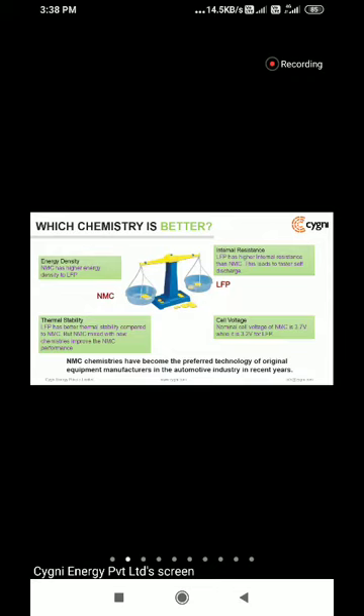Even when we look at the previous slide, the thermal runaway parameter is also not too far apart. LFP has thermal runaway at about 270 degrees centigrade, and NMC has it at about 260 degrees. Typically, all batteries, even when operating, we definitely do not go close to that in operation. We normally operate at about 60 degrees centigrade, which is the maximum we can think about in our field.